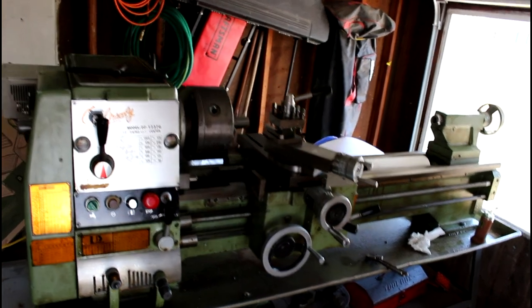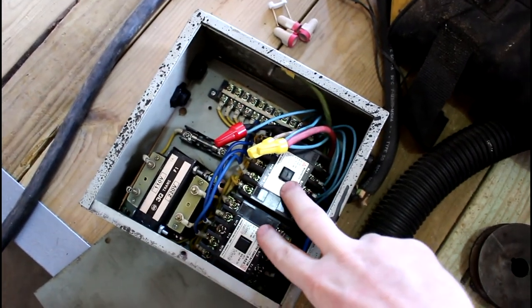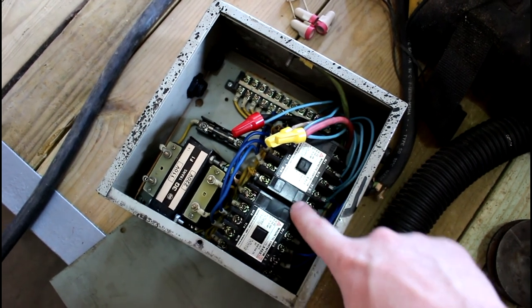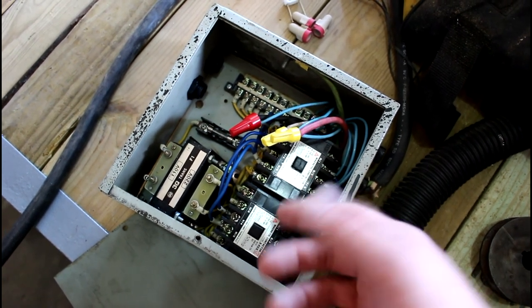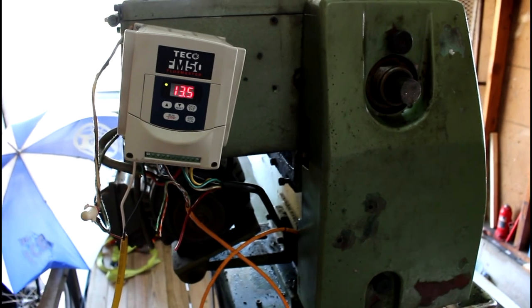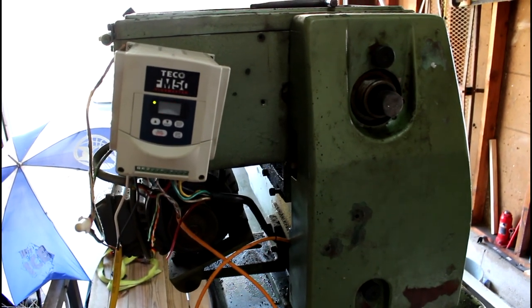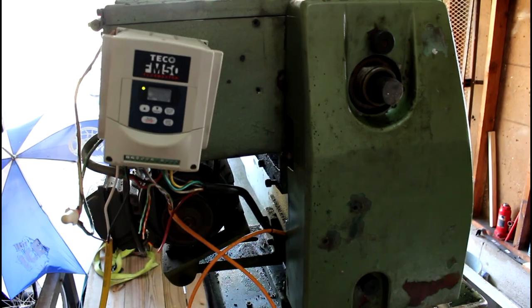It's just temporarily wired right now. Here's the old click-clack relay box that used to be in there — these are the reverse mechanisms. For three-phase, they click and clack back and forth on the switches to reverse the motor. What I put on there instead is a Teco FM-50, up to two horsepower, 220 volt in, three-phase up to 240 out, and I've got all my remote wiring hooked up.